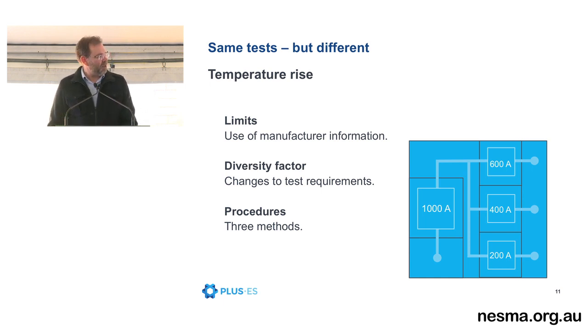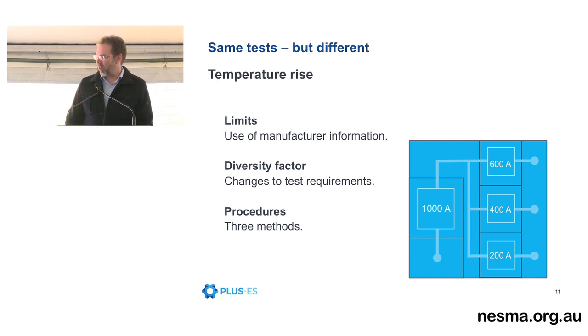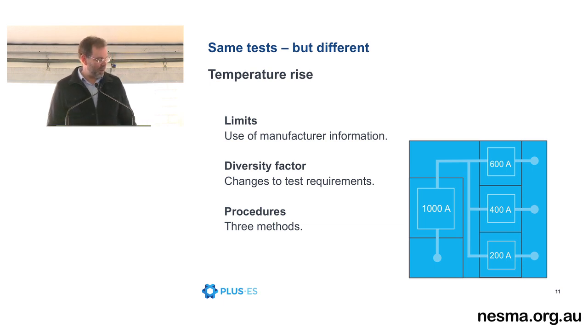Now, Australia has the opportunity to have an 80k limit on circuit breaker terminals when they have a piece of bus bar going to it, but we require a manufacturer to support that 80k limit. So the additional notes in the table, in our opinion, support that requirement, and so that's probably a fine difference, but nonetheless it is a difference. So if you want to put 80k on your outgoing circuit breaker terminals, we need a piece of paper to back up saying that that's okay.